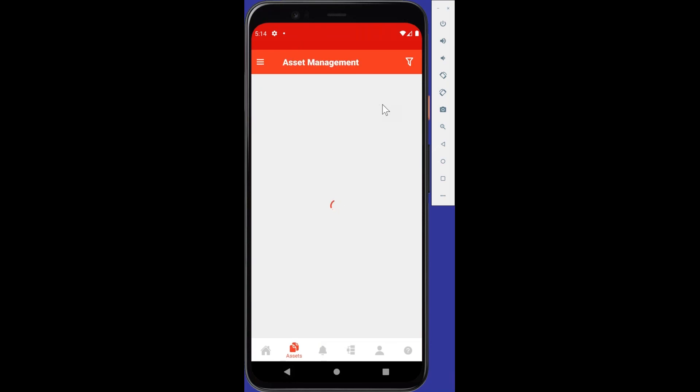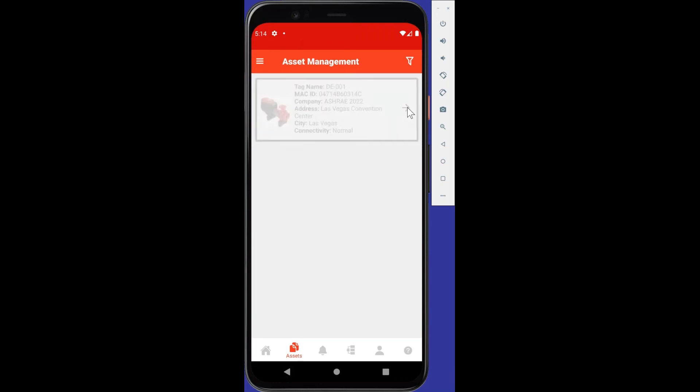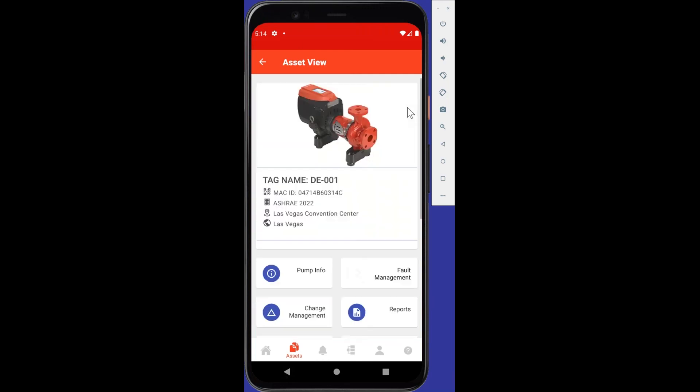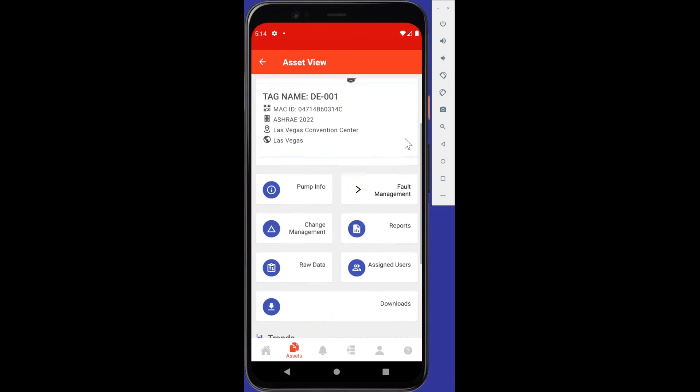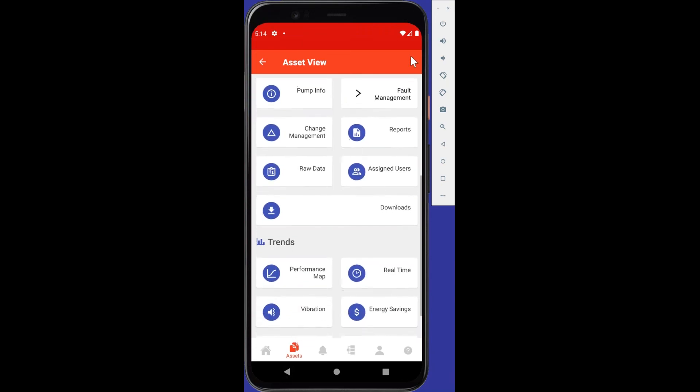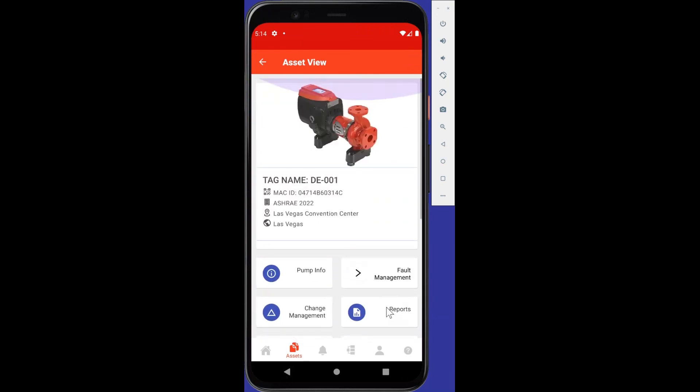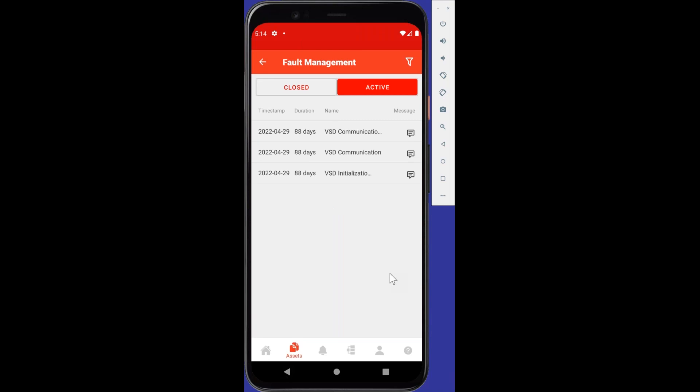So when we click it, it will show this pump here in the Las Vegas Convention Center. Maybe that was one of the pumps we had during the ASHRAE show earlier in the year. That's okay. This is just a demonstration here. So if I go ahead and click this guy and I hit next, let's see what it shows us. It looks like it's going to bring us to the asset view page, like I mentioned earlier. And again, it's showing us all the different modules here that are associated with that pump. But really, we want to see the fault management, which I didn't show you last time. And it's showing that this pump has active alerts going back to March or sorry, April. 4 is April, April of 2022, and for the last 88 days or so, it's been having some VSD communication errors. So we're able to navigate that.